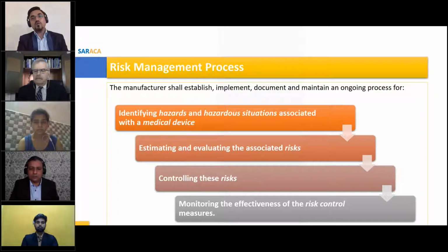What are the risks associated with our device, and how much effect or impact do they have on our device? So you need to estimate or evaluate those risks. Then controlling these risks, this is where risk management activities come into effect. You need to minimize or mitigate your risk. Whenever I say controlling, it means you need to minimize your risk. So controlling these risks is very much required. You need to follow the risk management process and risk control measures to control, minimize or mitigate your risk. Then you can monitor the effectiveness.